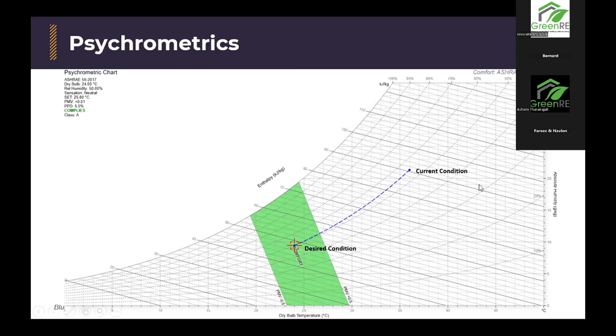So this is what I meant. This is your current condition. Let's say this is an outdoor system. You're just bringing in fresh air and you want to cool it down right down to space condition. This is where you are, the current condition: outdoor temperature around 36 degrees C. The RH is between 50 to 60, so around 55. We're planning to bring it all the way here to a cool 24 at the 50 mark, what we always like to have it at. So how do we go about getting it from there to here?